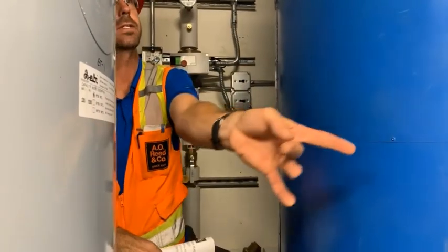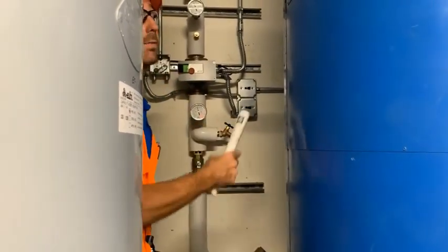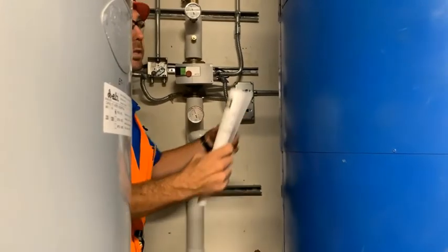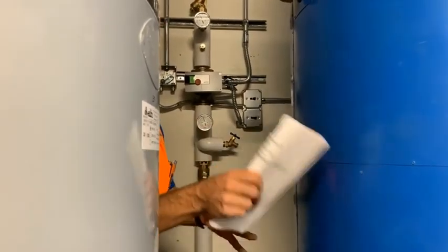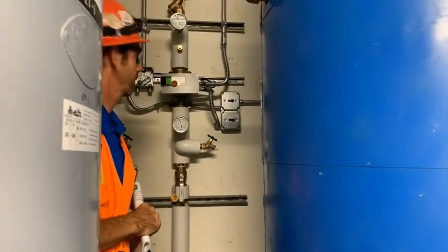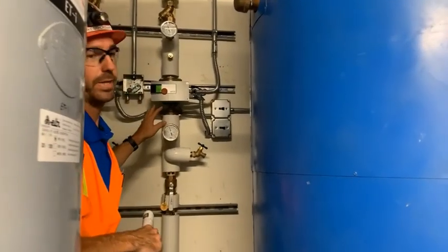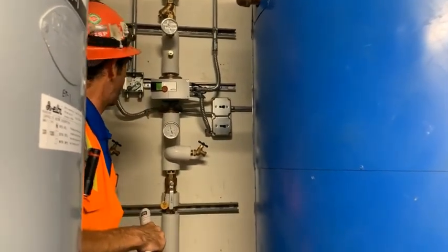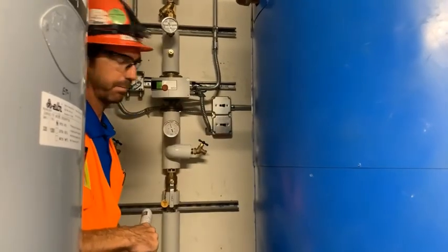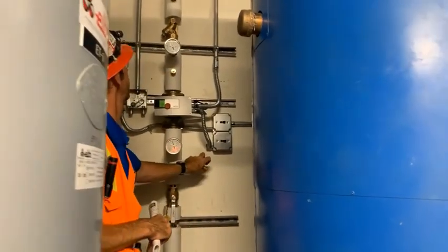There's a floor drain in between the tanks. Yeah. And just open these things up. I'd even run 2 hoses. The more flow you get, the better. The more air you're gonna pull down and bleed out of the system, okay? Circ pumps, when you're done with that procedure, make sure you open the valves back up and then turn on the pumps, okay? So these are the hose bibs that I was talking about right here.